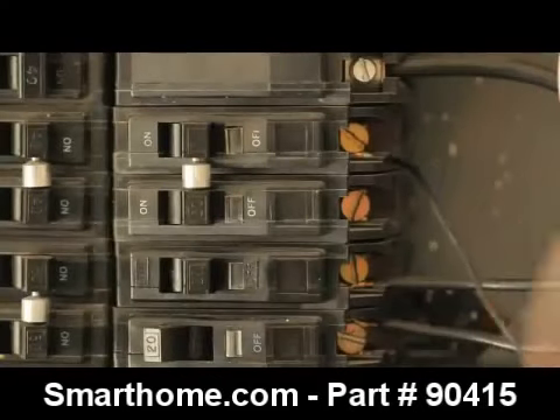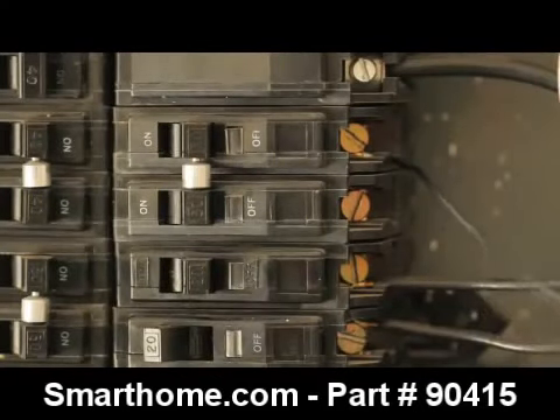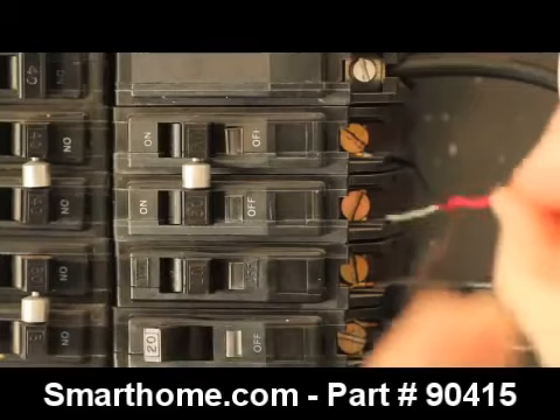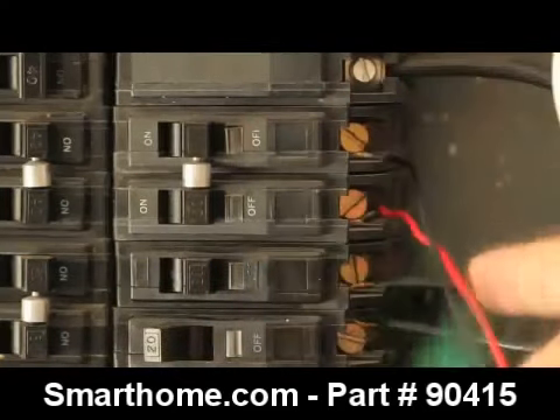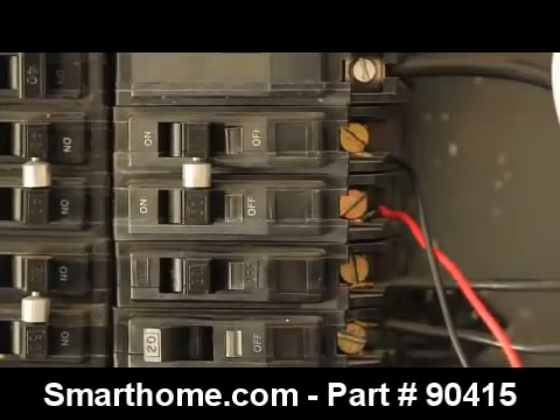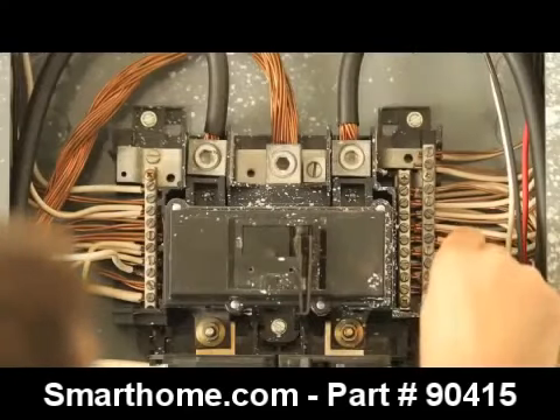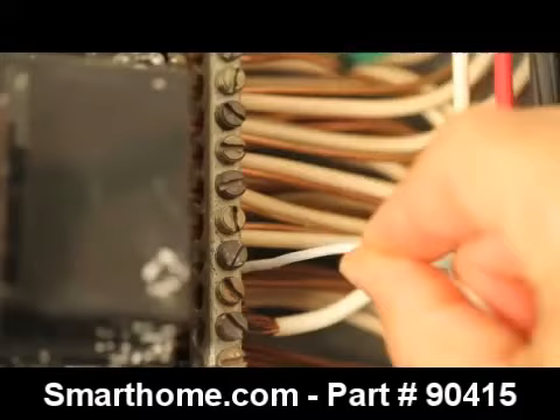Note that the black and red wires must create a 240 circuit. They cannot be connected to circuit breakers on the same phase. Going down the breaker panel, every other breaker is either A or B phase. Next, connect the white wire from the MTU to the neutral bus on the panel.